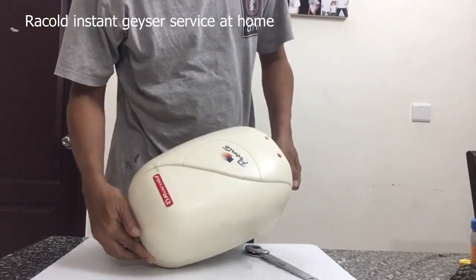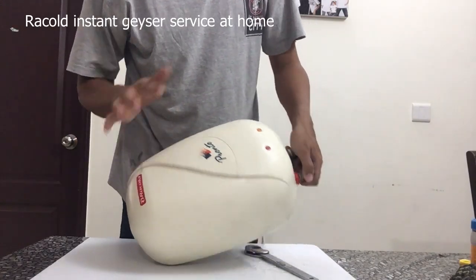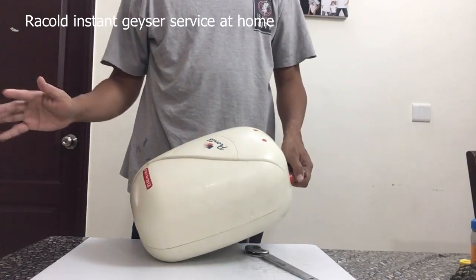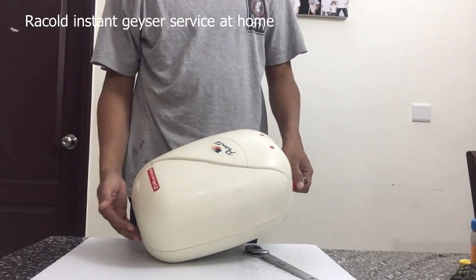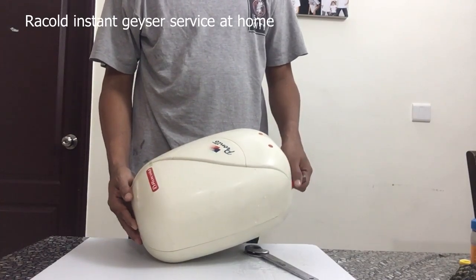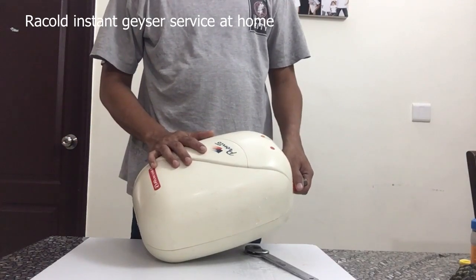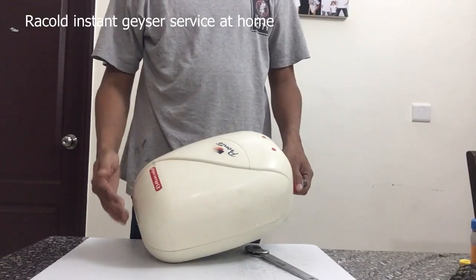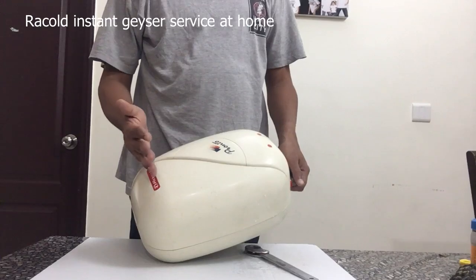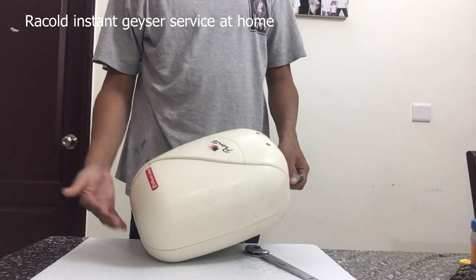This is a Racold Pronto instant geyser. The story is the same for all geysers over a period of time. This was last serviced about two years ago and there's a whole lot of salt and minerals in the water which tend to accumulate inside the tank, reducing the efficiency over time. It reduces the capacity and the heating time increases.